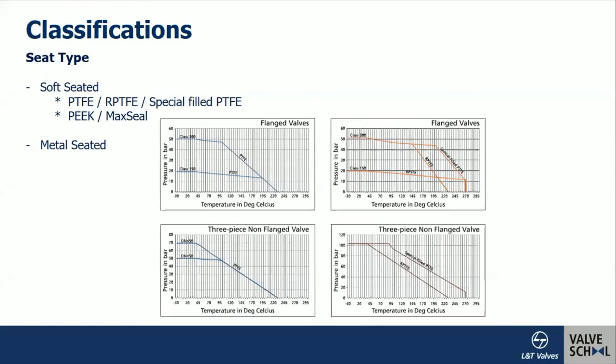The metal-seated variant uses a ball and seat made from 13% chromium steel or stainless steel hard-faced with stellite or tungsten carbide coating, to provide higher hardness and better wear resistance. It is important to note that when selecting a Class 800 ball valve with a soft seat, the valve is derated to the temperature and pressure limits of the seat material — not the full body class rating.